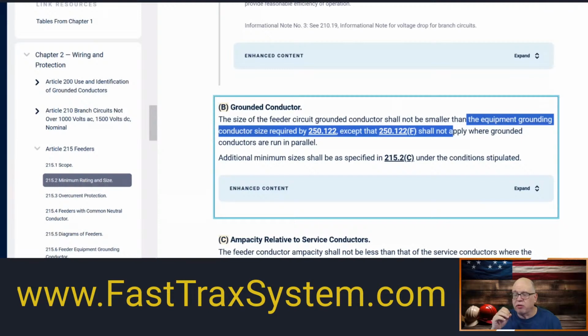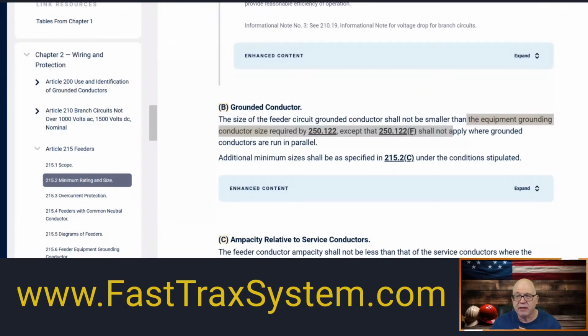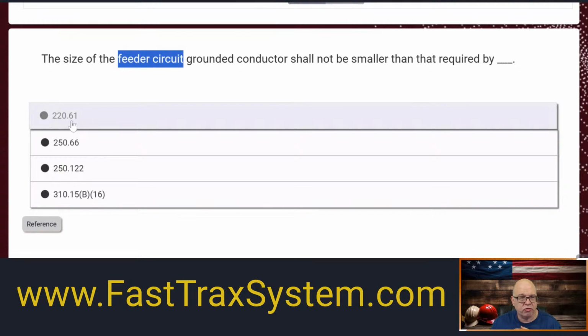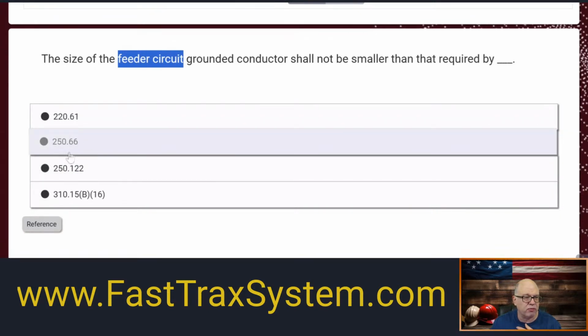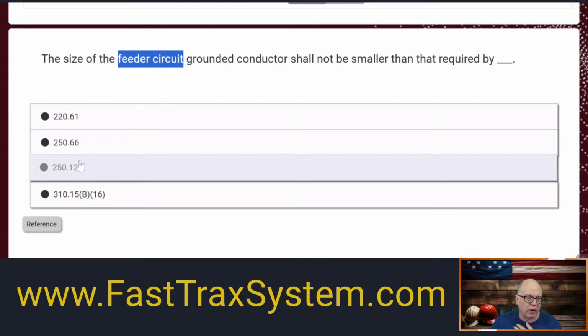And that's where people go down that rabbit hole and they would have selected 220.61 for some reason. And you know right off the bat it's not going to be 250.66, because that's the grounding electrode conductor sizing. And it used to be that 250.102(C) directed you to 250.66, but that went away. So this is the one that answers the question.